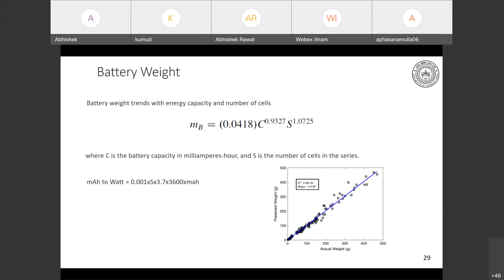So what is this power and C rating? What is the meaning of the C rating? These batteries are rated for 10C, 20C, 40C, and so on. What it means is the time it takes to discharge the entire battery. So if the time of discharge is 5 hours, the C rating for the battery will be 1 by 5. If I can discharge this entire battery in 1 by 5 hour, which is 12 minutes, then the C rating is 5.